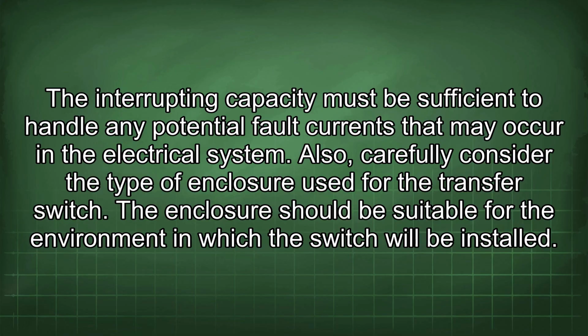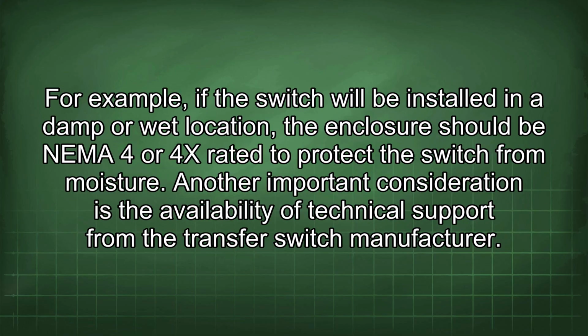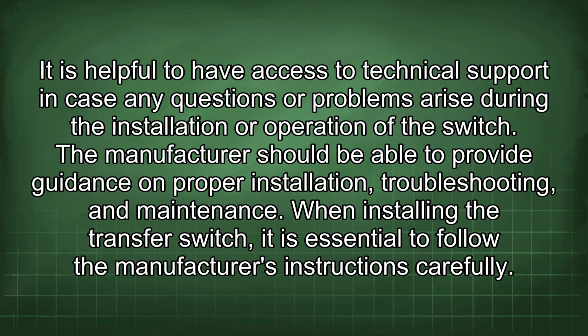Also, carefully consider the type of enclosure used for the transfer switch. The enclosure should be suitable for the environment in which the switch will be installed. For example, if the switch will be installed in a damp or wet location, the enclosure should be NEMA 4 or 4X rated to protect the switch from moisture. Another important consideration is the availability of technical support from the transfer switch manufacturer. It is helpful to have access to technical support in case any questions or problems arise during the installation or operation of the switch. The manufacturer should be able to provide guidance on proper installation, troubleshooting, and maintenance.